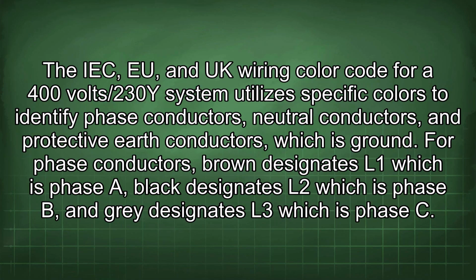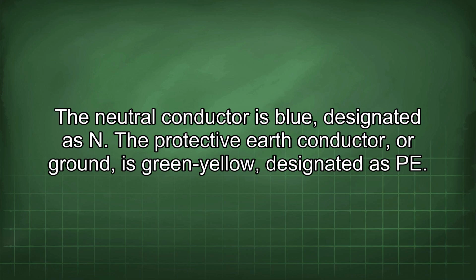The IEC, EU, and UK wiring color code for a 400V/230Y system utilizes specific colors to identify phase conductors, neutral conductors, and protective earth conductors, which is ground. For phase conductors, brown designates L1, which is phase A, black designates L2, which is phase B, and grey designates L3, which is phase C. The neutral conductor is blue, designated as N. The protective earth conductor, or ground, is green-yellow, designated as PE.